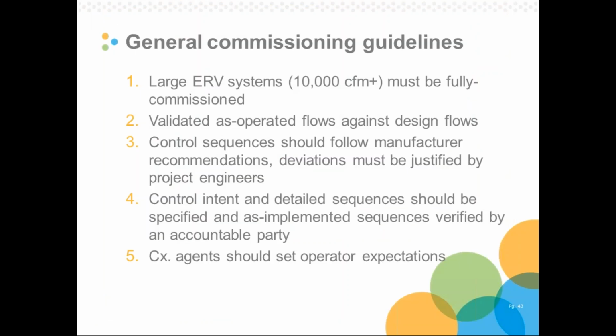So I want to give some general commissioning guidelines too. First of all, large energy recovery systems have to be fully commissioned. We showed early on that all the flow moves through these systems. If we're considering energy savings from energy recovery in the state of Minnesota, we've got to go after the big units. I'll say right now that there were clearly units in our study that were big that were not commissioned, and about 50% to 55% of the issues that we found would have been discovered and fixed in a commissioning process. We have to put some additional burden on the commissioning agents too.